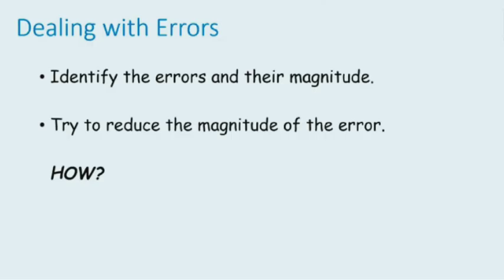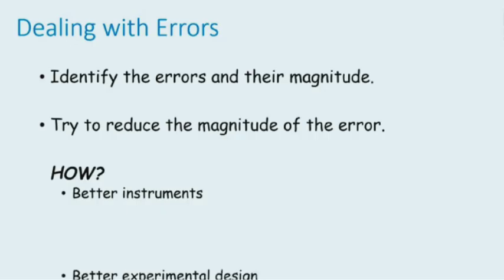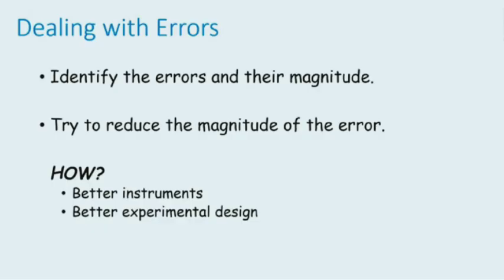So how do we do this? How do we mitigate these errors or check? One, as I said, is in the instrument: see whether we can get better instruments, maybe instruments which have higher sensitivity, or see that their calibration is done regularly and calibrated by a certified agency, those who are certified with 17025, etc.